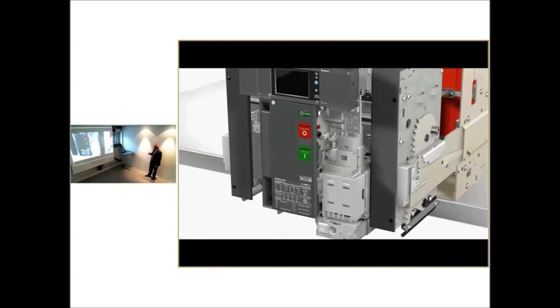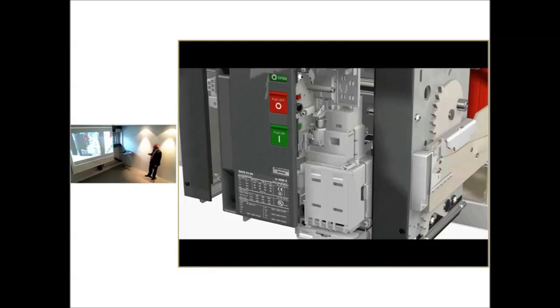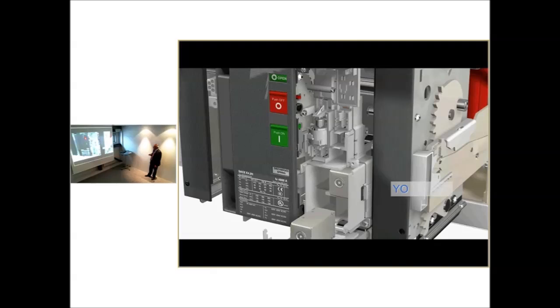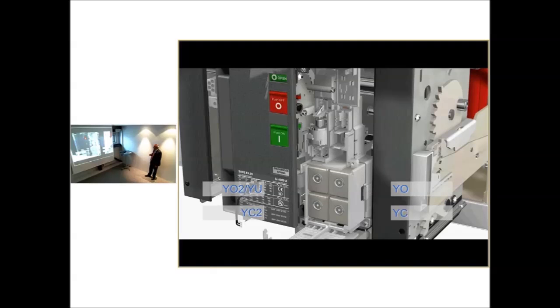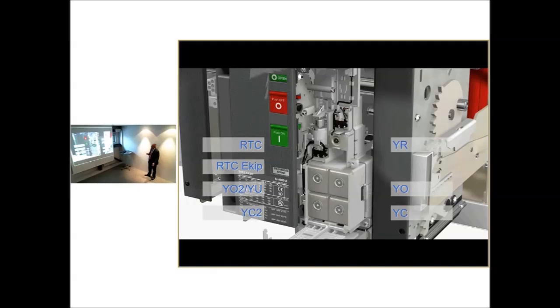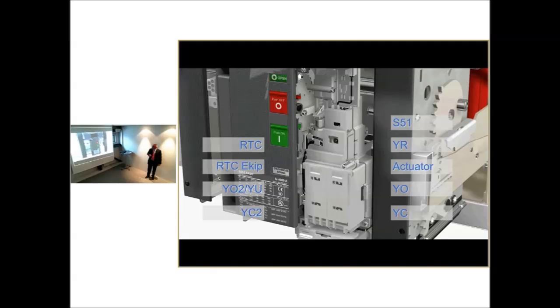Everything here is enclosed. Now you have a cage for the 4 coils: opening coils, closing coil, double opening or undervoltage, and closing coil. So you have total redundancy on that. Then the ready-to-close contact. Here you have the possibility to put the reset. The reset can be done remotely. Before, it was not possible. And then you also have the actuator to open and close the breaker with communication.